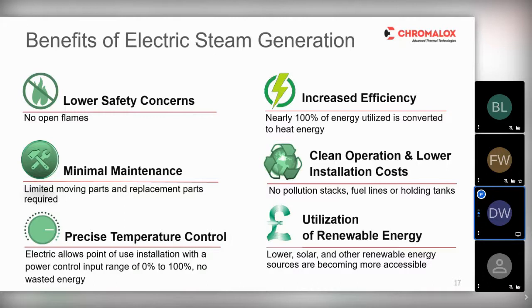And a traditional fossil fuel burner is typically going to operate with an efficiency level of approximately 85%. Whereas an electrical element is going to operate with an efficiency level of very, very close to 100%. And a traditional fossil fuel burner has an efficiency that depends upon a number of different assumptions, such as the percentage load it's operating on, demand cycling, seasonal variation, soot build up on nozzles, for example. And they're also sized upon an assumption that the boiler is operating at full load capacity. Therefore, that efficiency level is going to fall whenever the demand for steam falls.